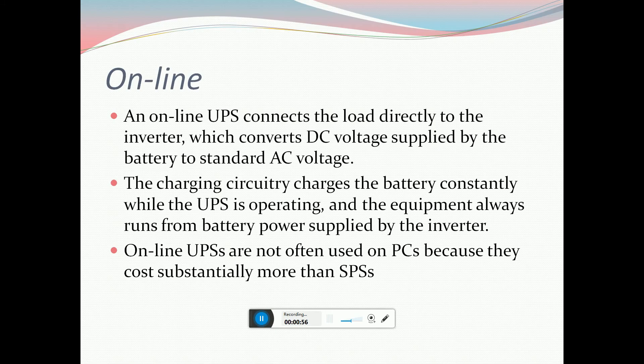An online UPS connects the load directly to the inverter, which converts DC voltage supplied by the battery to standard AC voltage. The charging circuit charges the battery constantly while the UPS is operating, so the equipment always runs from battery power supplied by the inverter. Online UPSs are not often used for PCs because they cost substantially more than SPS units.